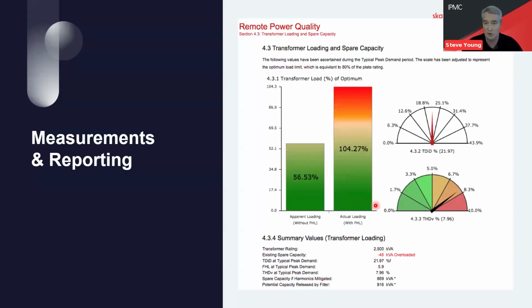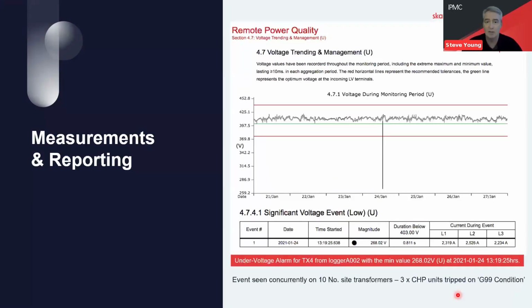And ultimately, because we've gone over where we should be, the voltage distortion value has gone over the 5% recommended limit, and we're getting up towards 8%. And useful reporting like this can give us some very valuable insights on what we can do about it and the spare capacity that we can regain. Similarly, we can pick up short duration events like this one.